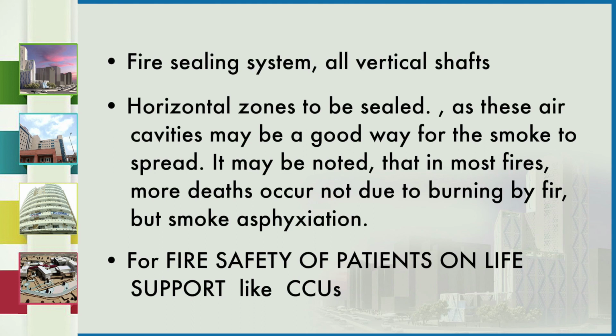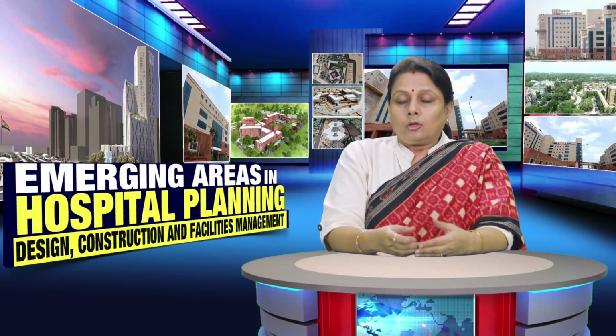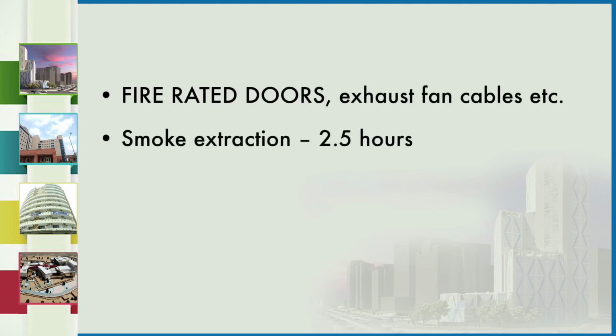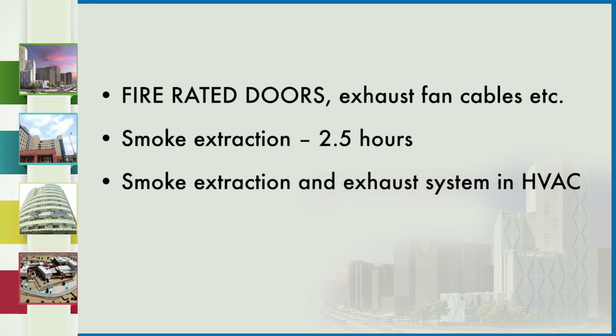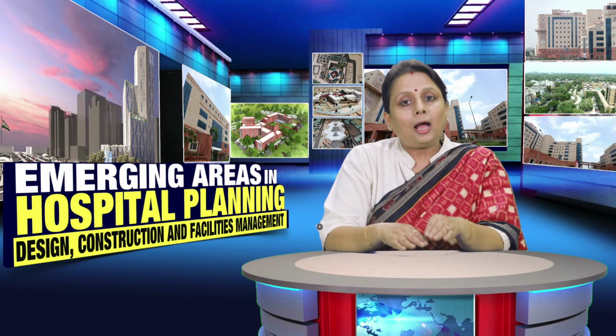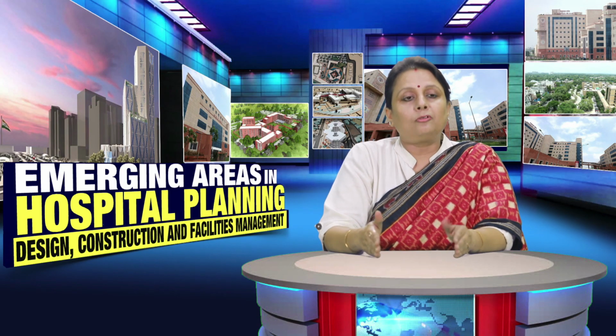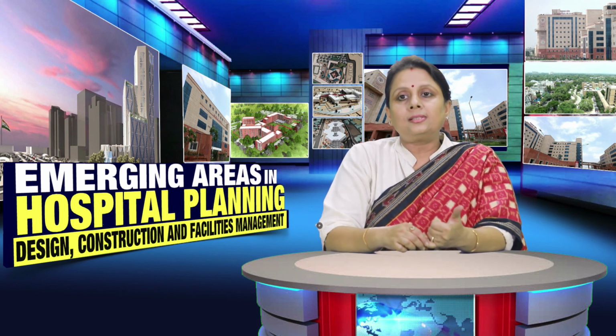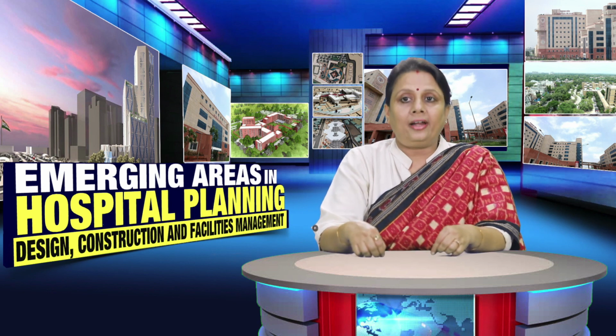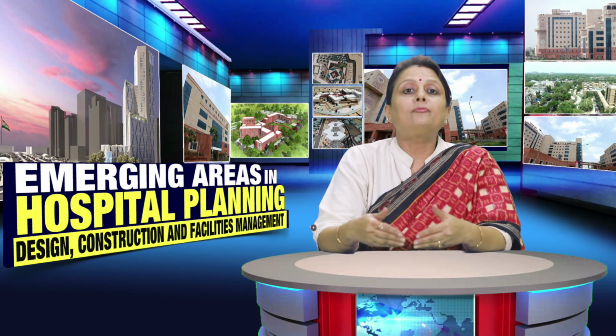For fire safety of patients on life support like CCUs, there are different methods. These people cannot be moved out. So we have to use fire-rated doors, and we have a system of smoke extraction in those areas itself. These patients will be kept inside there till the fire is taken care of or is completely subdued. So the HVAC system is designed in a way that it will continue to get fresh air and the smoke will get exhausted out, apart from the fact that the doors are also fire rated, so the fire cannot come in. One important point to note is that even the cabling in the exhaust system has to be fire rated. Otherwise, the cable itself will burn out and the system will not be effective anymore.